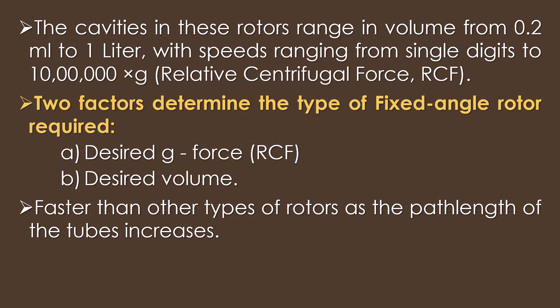Two factors determine the type of fixed-angle rotor required: the desired g-force and the desired volume. Fixed-angle rotors are faster than other types of rotors as the path length of the tube increases.